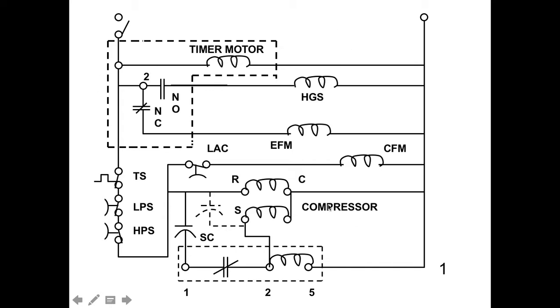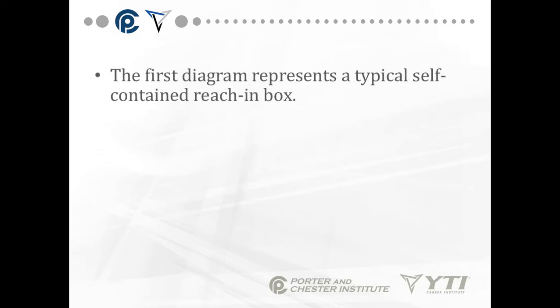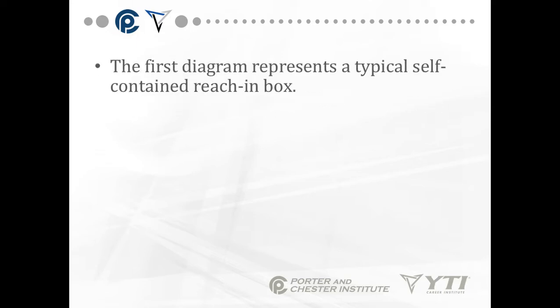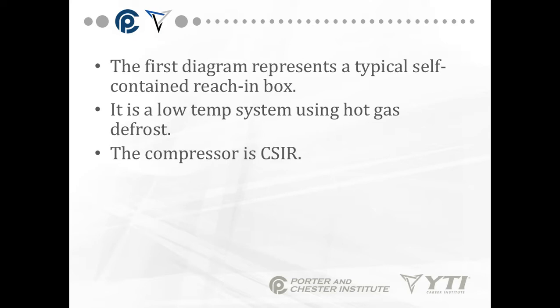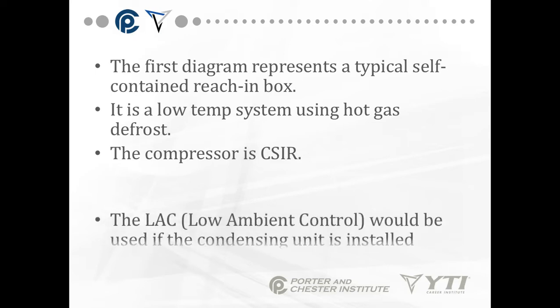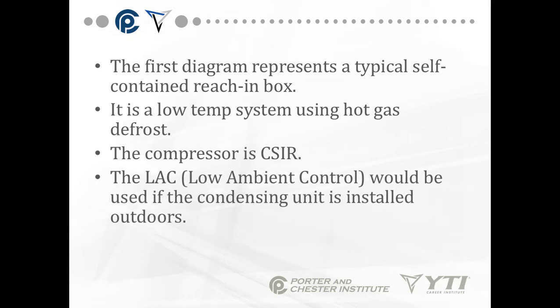The first diagram represents a typical self-contained reach-in box. It's a low temperature system using hot gas defrost. The compressor is a CSIR motor, capacitor start induction run. There's a low ambient control that would be used if the condensing unit is installed outside. The run cap is optional.